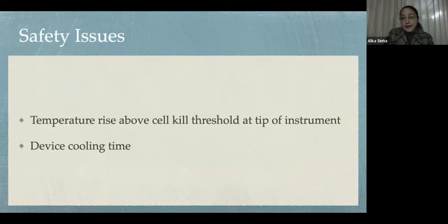Even though there's very little thermal damage, there are safety issues because the temperature rises significantly at the tip of the instrument, and this can be above the threshold for cell kill. So inadvertently, if we touch any organ with the tip of the forceps, it can lead to ischemia. We have to remember that there's a device cooling time, by which time it cools off sufficiently to obviate any injury due to the heated tip.